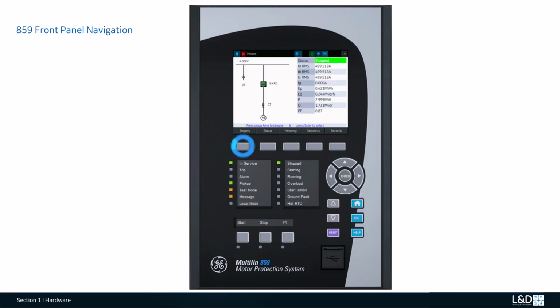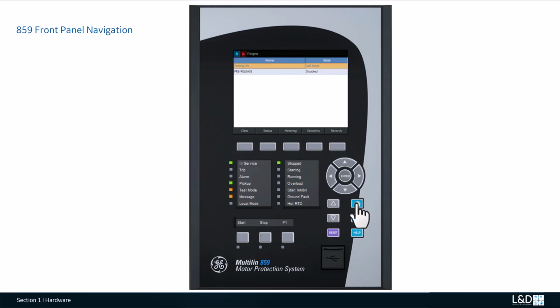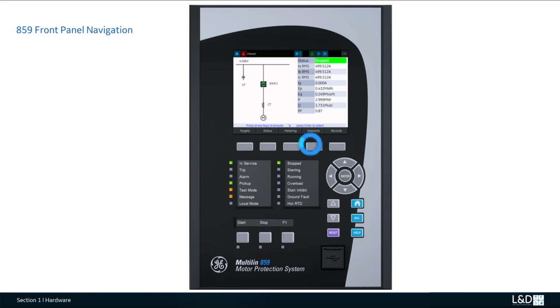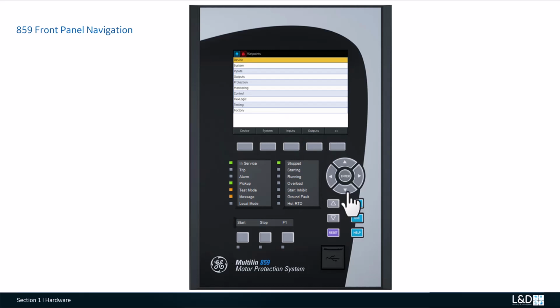If any element operated, we can click the button, and there is no target operated for this one, and we can check the set points. Those are all the set points, for example the system, inputs, outputs, and the protection. We can just use the arrow key, or press the arrow key and the tab key to navigate. It's two-way. You can press this arrow key down, it will highlight, or we can press this one to go to the next.